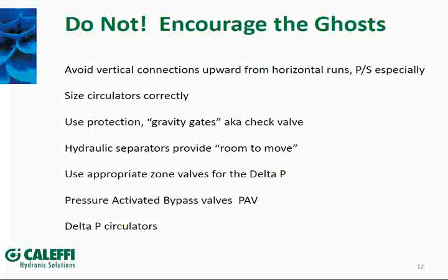'Gravity gates' is a European term — a lot of solar components have what they call gravity gates, which is just another word for a check valve. A hydraulic separator is another way to prevent this: if you've got two different piping circuits with different-sized pumps, a hydraulic separator can isolate the two flows and prevent flow crossing into the distribution side when you don't want it.